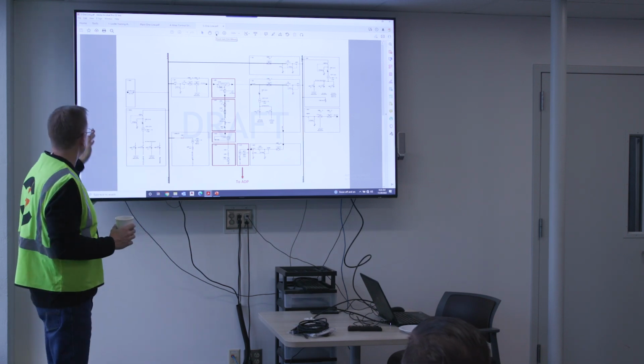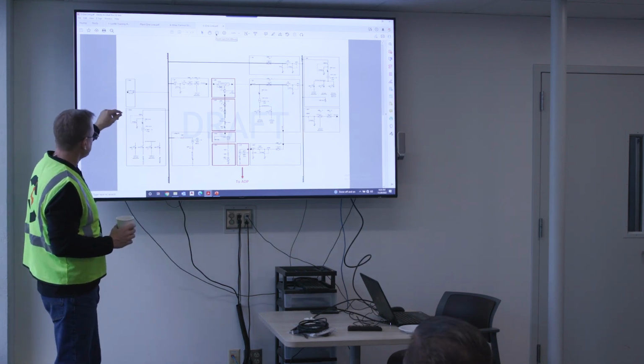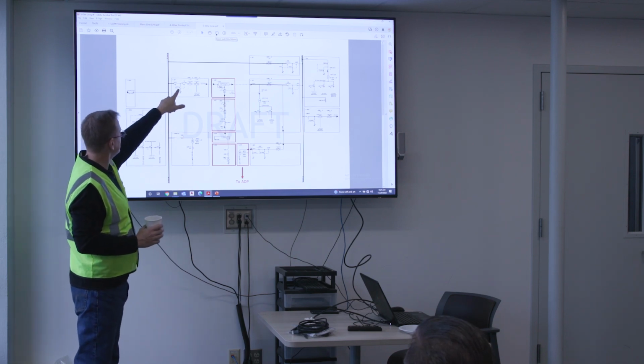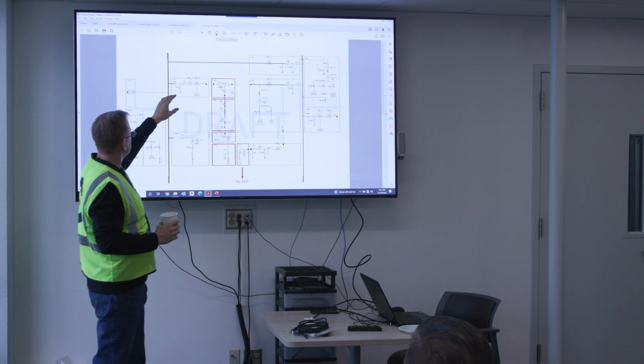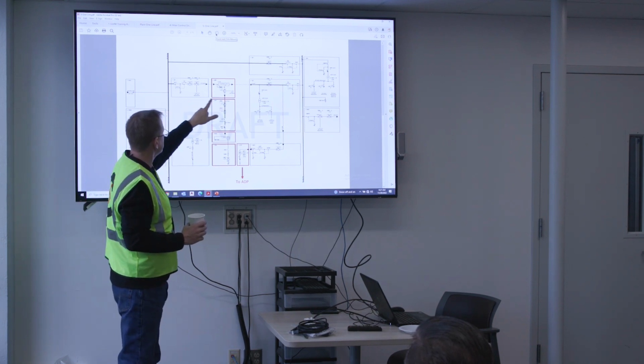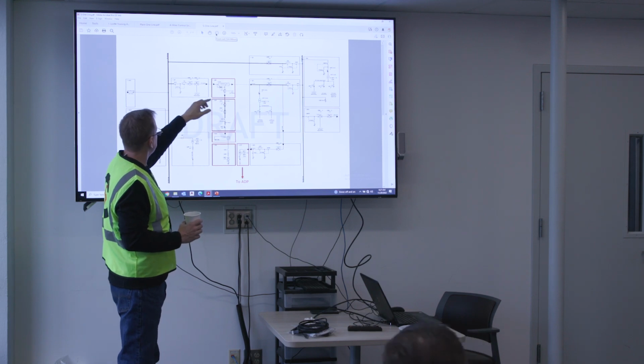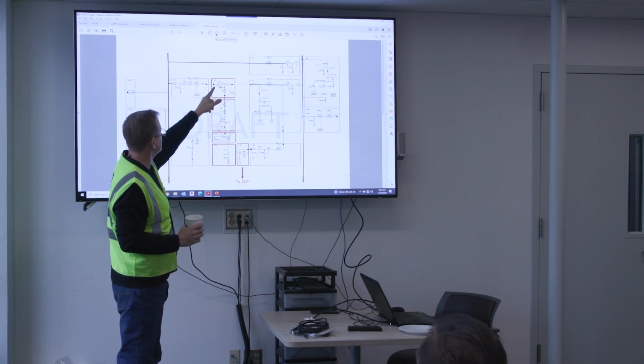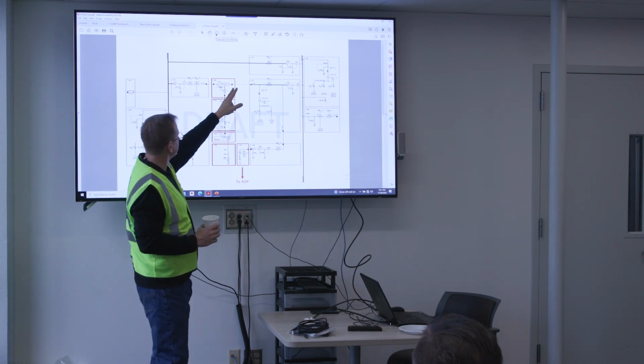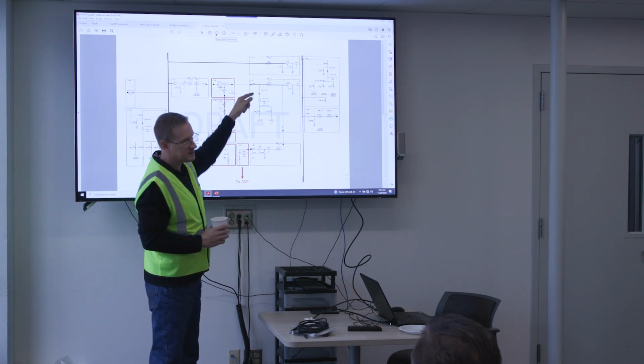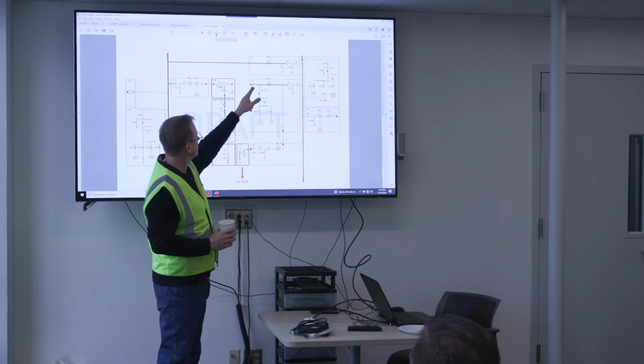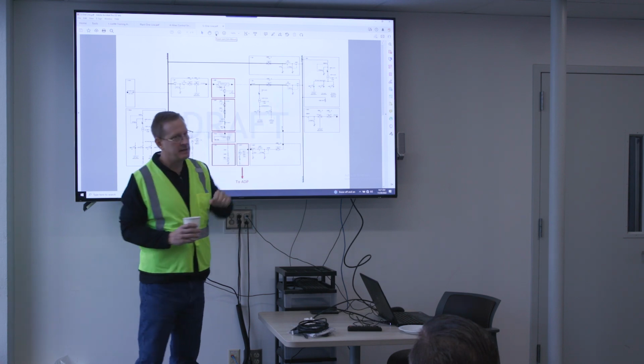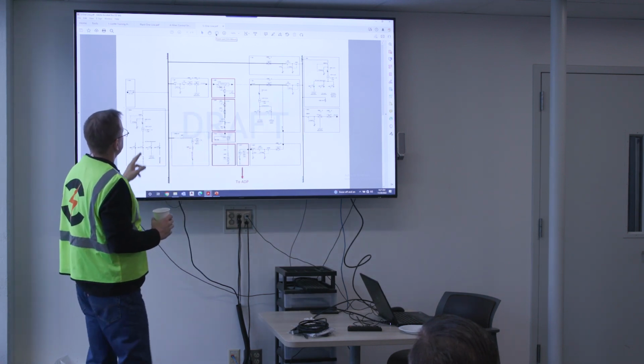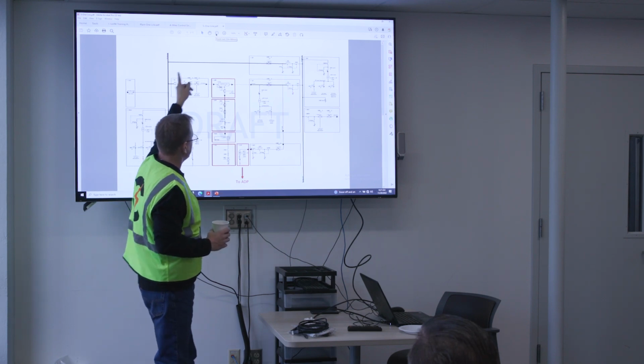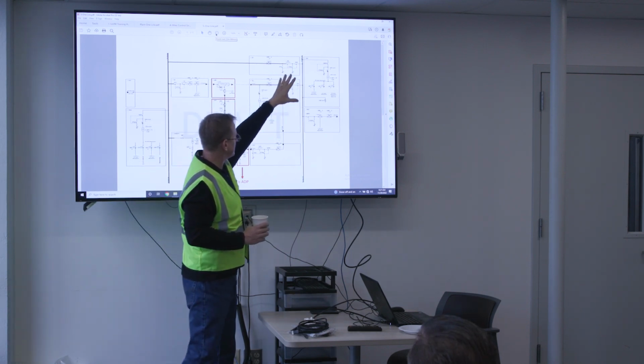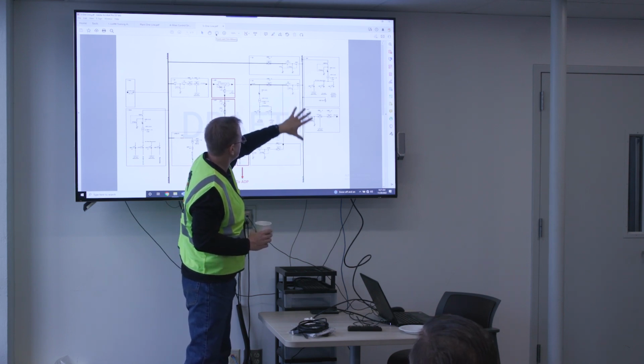So what we've got here coming in is our utility. We've basically got an input bus here. Here's our Q1 breaker. Then we come through, and this is our choke, which is external to the switchgear, so it's in red. We have a cable connection from this point to the input of the choke, and a cable connection from the output of the choke going back into the switchgear, into the line side of Q2. That's our Q2 output breaker. Then we've got our bypass that bypasses around the system with our Q3 breaker. And we've got an output bus here.